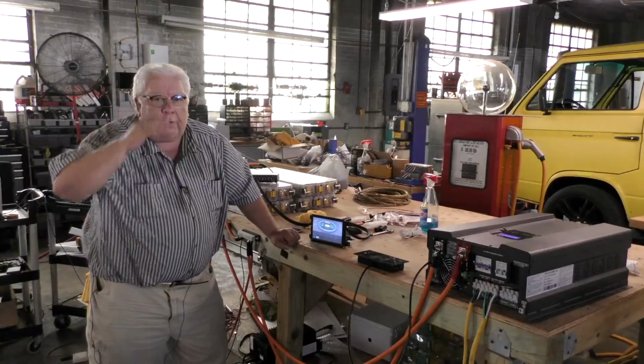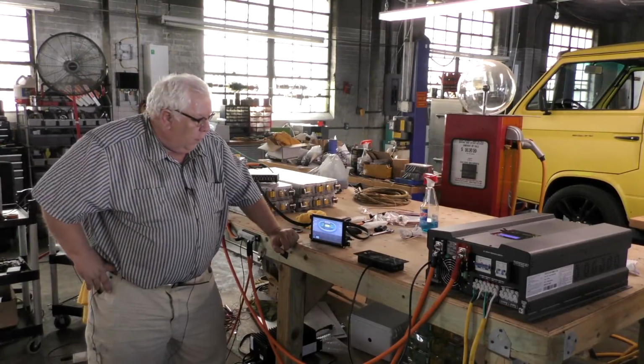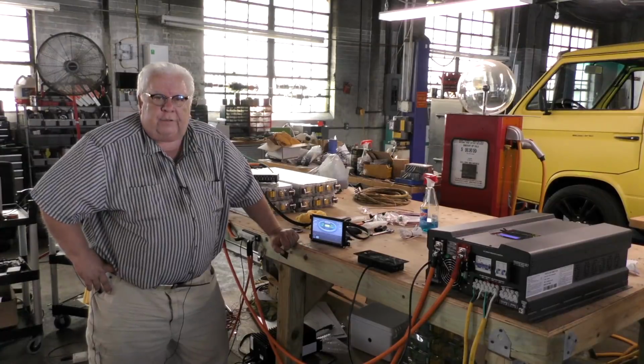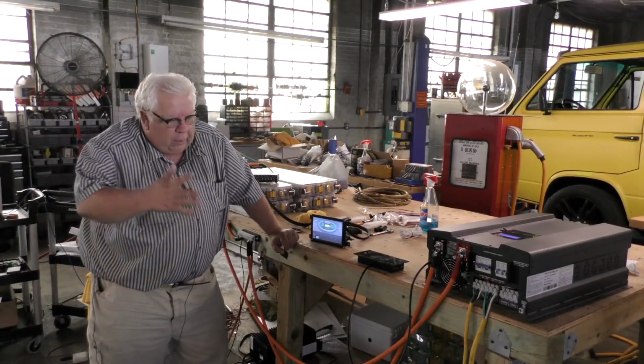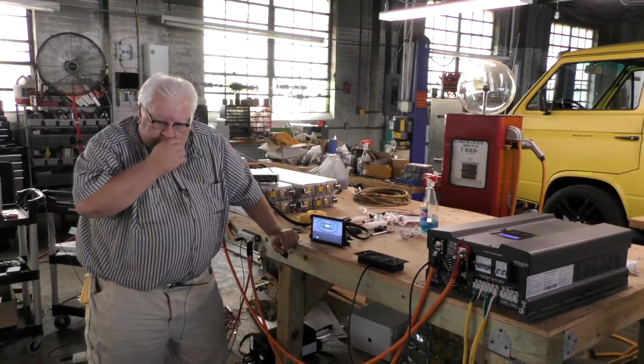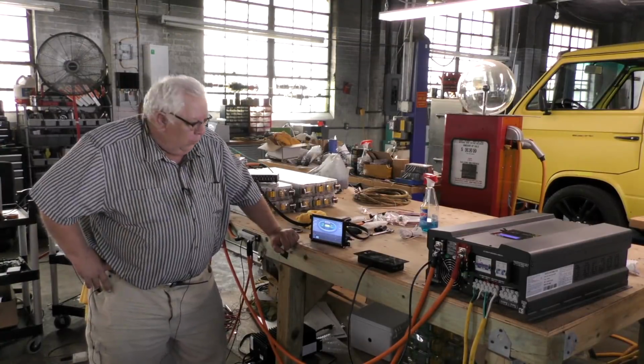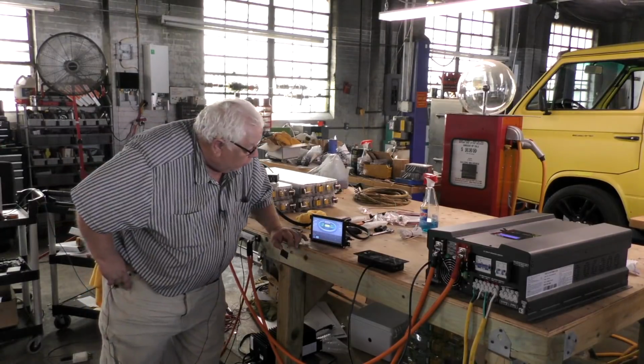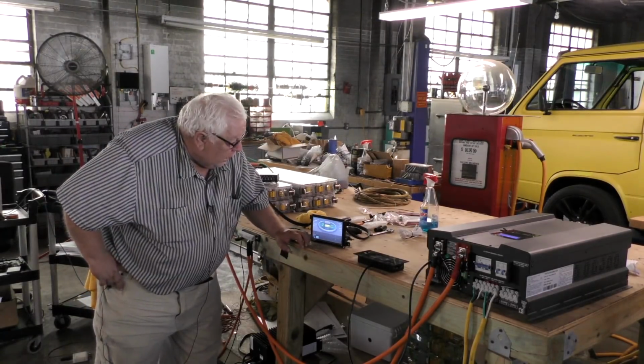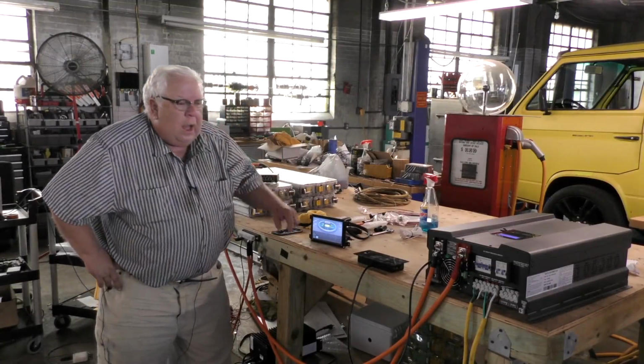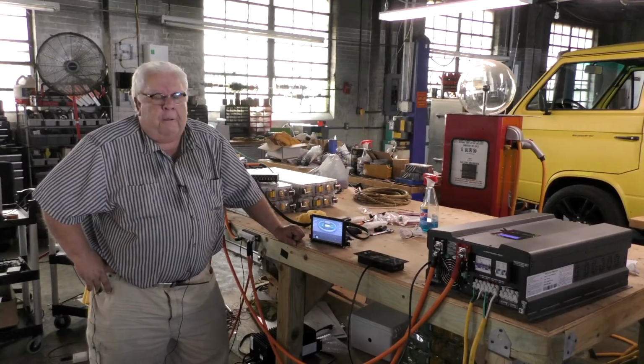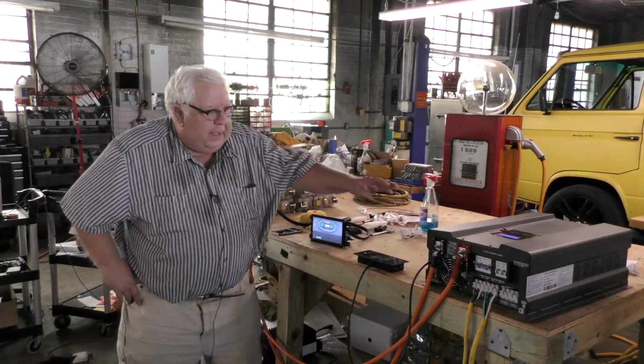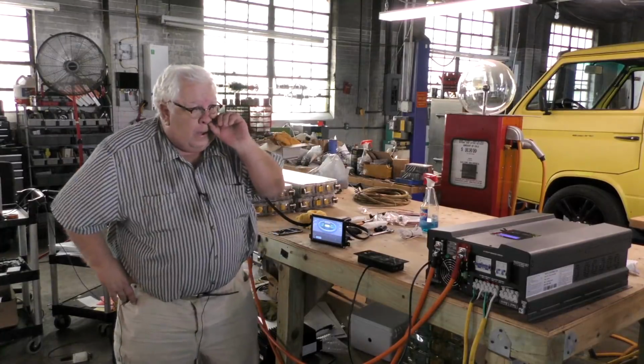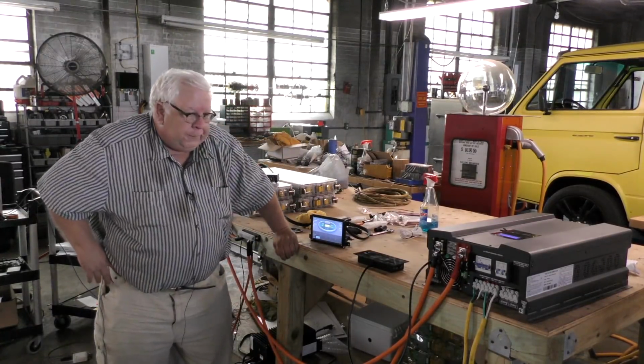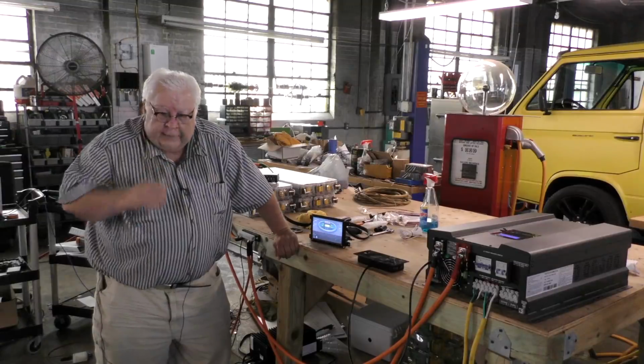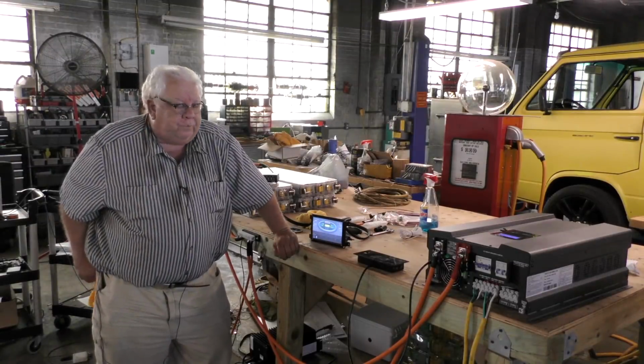And at this point, we're producing more power out of the Solar Edge than we're actually using in the shop. And without noise or any particular excitement, we've started charging the batteries. We're at 43% and we're putting 14 amps, 13 amps of energy into the battery. Now, understand that this is still making our waveform. It is what our Solar Edge is synced to in phase and frequency.